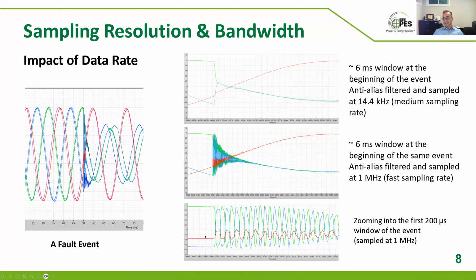The question becomes, so what? What is it good for, what is not? Later you see something like this allows you to locate the fault. This 8 microsecond, or 4 times 2, basically says the fault happened 4 microseconds of traveling wave time away from this terminal, which puts the fault at 1.2 kilometers from this terminal. It allows you to locate the fault within a few tens of meters in this case. But that's the information that's lost at a low sampling rate. I want to remind you it's not just the sampling rate; the instrument transformer or the sensor should also have the bandwidth, so as not to filter this sort of information out.